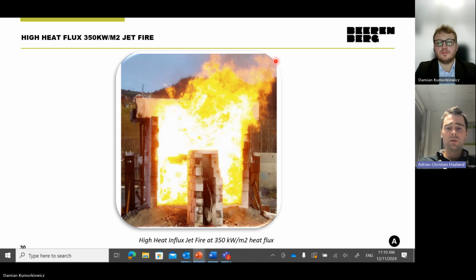As a result of this, you get heat flux up to typically around 350 kilowatt per square meter. But bear in mind that both for the standard jet fire test and for the high heat flux jet fire test, the heat flux will vary a lot. It's oscillating violently. It's not like a furnace test where you have a stable 1100 degrees throughout the test. In a jet fire, and especially in a high heat flux jet fire, you can have anything from 1000 degrees to 1450 degrees oscillating up and down.